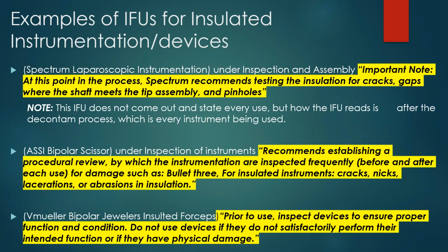So in this IFU, it does go into a little bit more detail of what you should be looking for based on damage. The ASSI bipolar scissor says it recommends establishing a procedural review by which the instrumentation are inspected frequently before and after each use for damage such as, and it had some bullets, and on bullet 3 it said for insulated instruments, cracks, nicks, lacerations or abrasions in the insulation. So here, again, another example of describing what the damage you should be looking for. The V. Mueller CareFusion bipolar jeweler's insulated forceps states that prior to use, inspect devices to ensure proper function and condition. Do not use these devices if they're not satisfactory and perform in their function or if they have any physical damage.